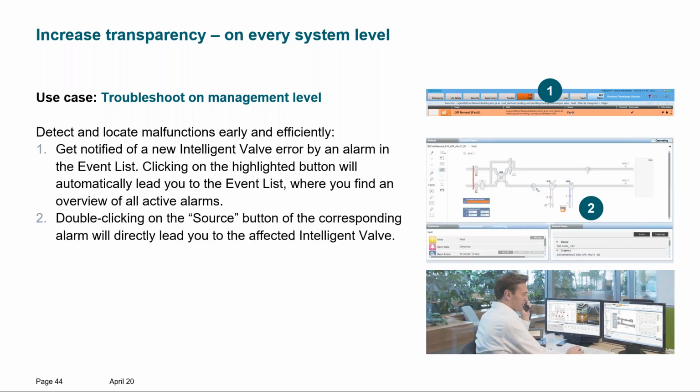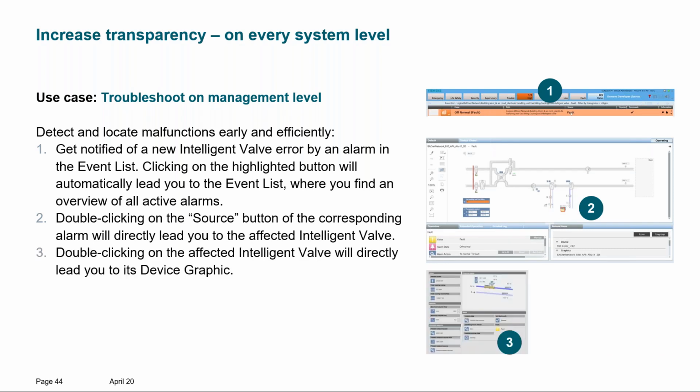You are guided through the building management system into the part of the building and then onto the device, and can see what's happening there locally. Maybe the actuator failed? Is the supply temperature too low? Is something stuck, like the position is fully open, but flow is not there? What is happening? Is the strainer blocked?